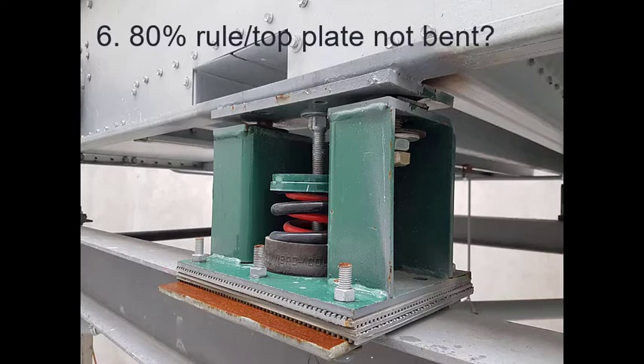There could be a problem if too heavy a load is placed on too small an area on the top plate, which could cause it to deform during installation before the springs are adjusted. This could lead to the hold-down bolts being angled and creating short circuits with the hold-down plates.